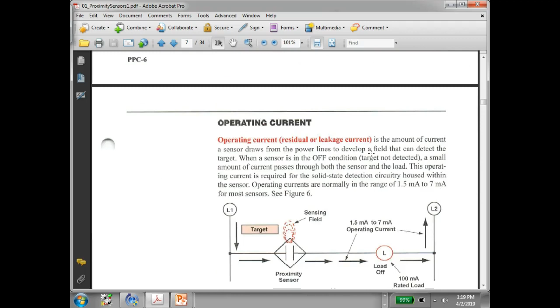The operating current is what it draws when it's not activated, and you measure that current. So it's going to be down in the milliamps, right? It's going to be really low. This is just what it takes to fire up the electronics inside the two-wire sensor. If you were measuring this on a three-wire sensor, you wouldn't measure it here. You would measure it up here in the line that goes to L2.